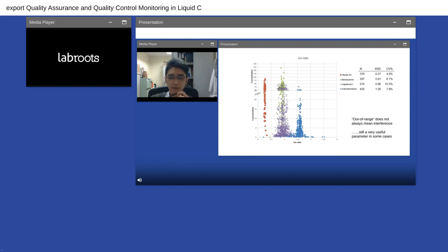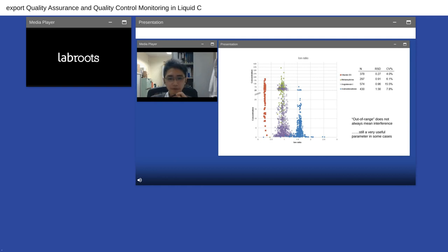One thing to note is that the ion ratio is concentration-dependent. When concentration approaches the LLOQ, the ion ratio will fluctuate. Different analytes may also show different behavior in ion ratio fluctuations. Looking at ion ratio distributions for molecules like vitamin D3, metanephrine, small peptides like angiotensin-1, and steroids — some are quite precise like vitamin D3 and metanephrine, while angiotensin-1 measured at low nanomolar or picomolar range shows wider distribution. When devising acceptance criteria for ion ratio, we must consider different behavior in different molecules. Out-of-range ion ratio does not always mean interference.